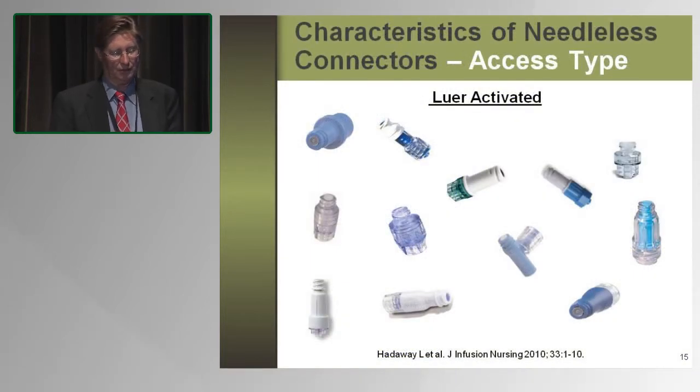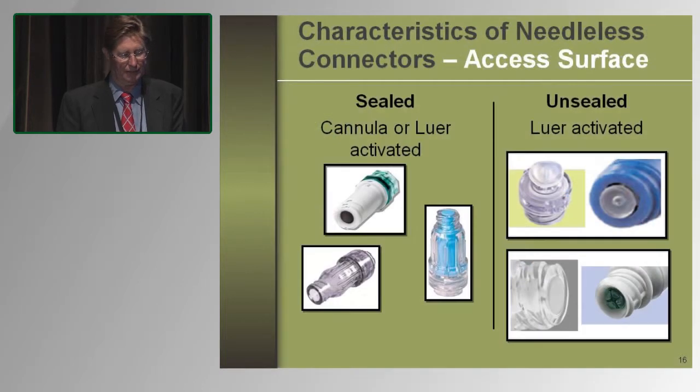If we look, there's a wide variety now of luer-activated mechanical valve needleless connectors, whether they be positive, negative, or neutral pressure. Some of them are sealed well, as shown here on the left, and others are not, as you can see there with a gap around the plunger, or here where you have a very complicated external surface where it is difficult to get your disinfectant down into those areas.